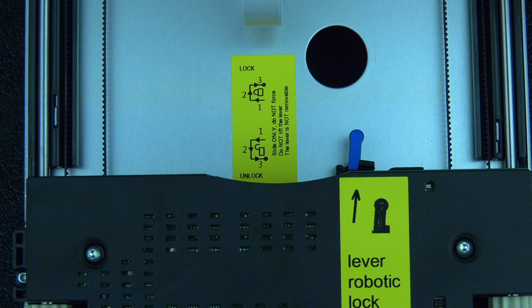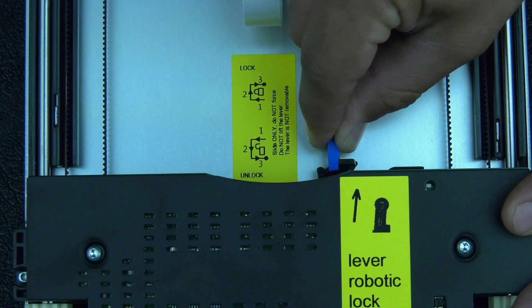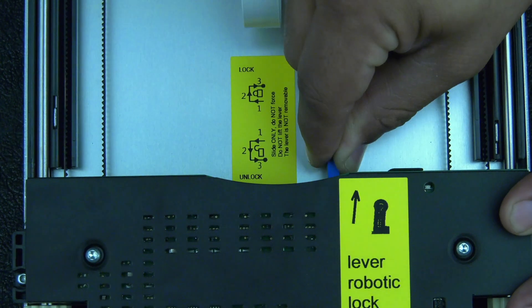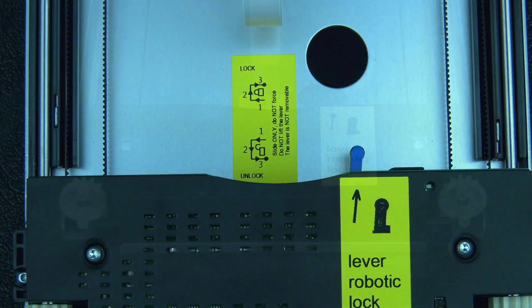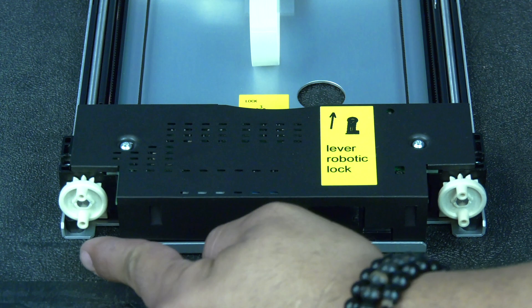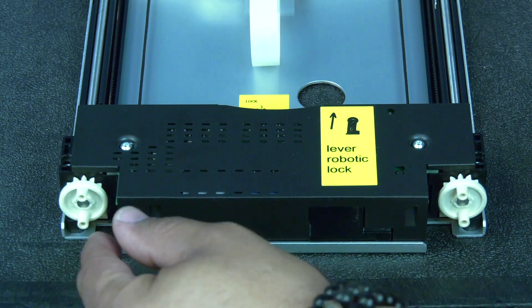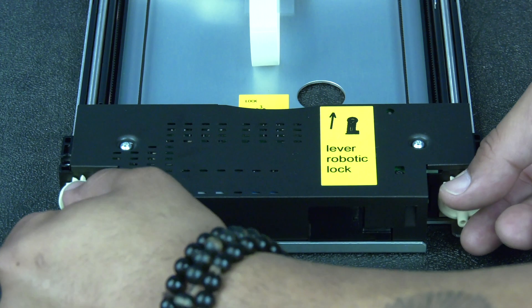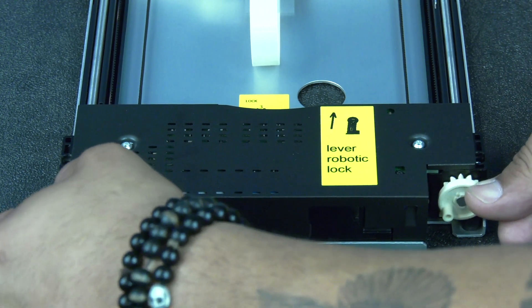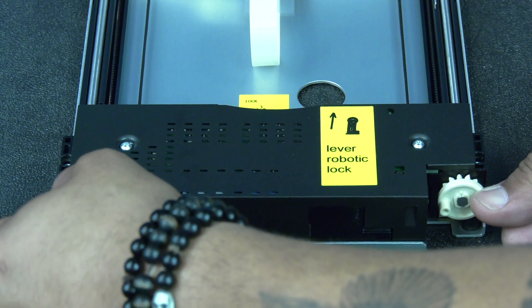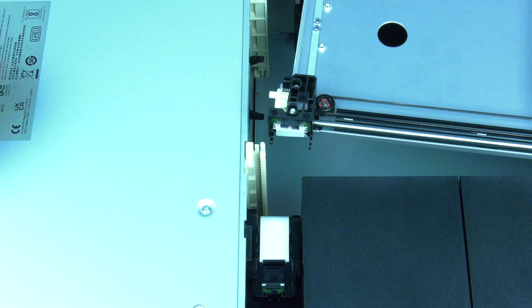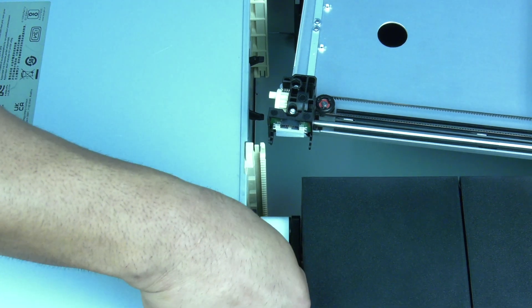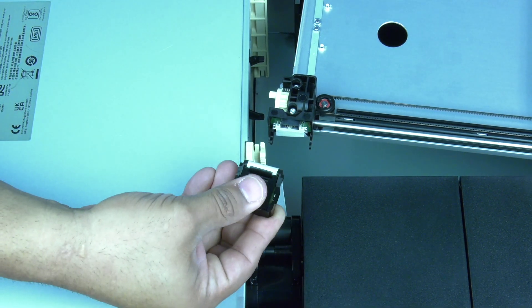First you need to verify that the robot is unlocked. Please examine the locking mechanism like you did earlier to ensure the robot is in the unlocked position before trying to install it. Now you will notice that each corner of the robotic assembly has a gear with two pins sticking out from it. Rotate one of the gears so that the pins are lined up horizontally at the three and nine o'clock positions. This should make all other gears do the same. Once all gears are aligned, rest the robotics assembly on top of the four tracks that the gears slide down on. The pins should be resting on the outside of the tracks.